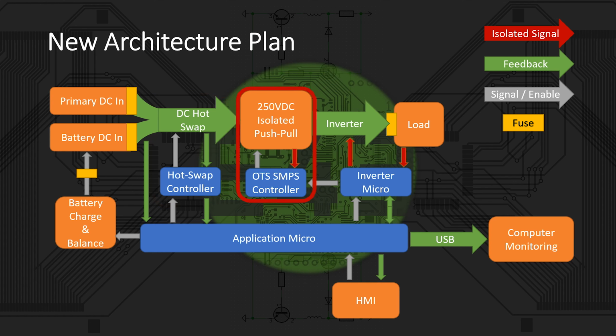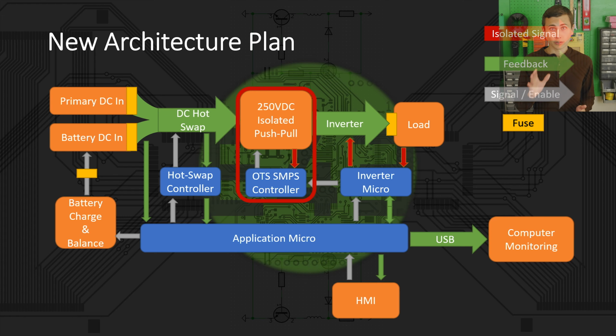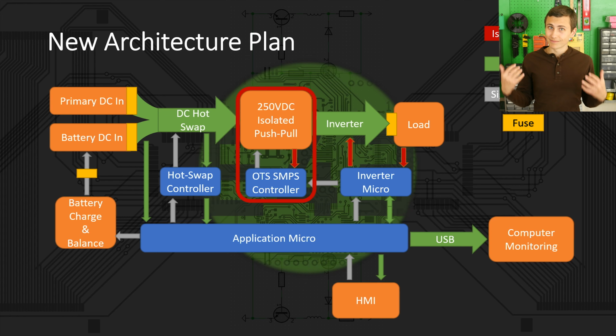This is critical since the DC to DC converter will soft start, bringing the common mode voltage slowly from 0 to 125 volts. This will allow the circuit breakers to open if there's an overcurrent fault due to equipment not being designed to handle common mode voltage between neutral and ground. In theory, the current here should be very small, but there's still voltage there. And since ground of the high voltage side is allowed to float, any current that's pulled should bring neutral closer to ground, but at very worst, this will be following neutral of mains with minimal current flow.